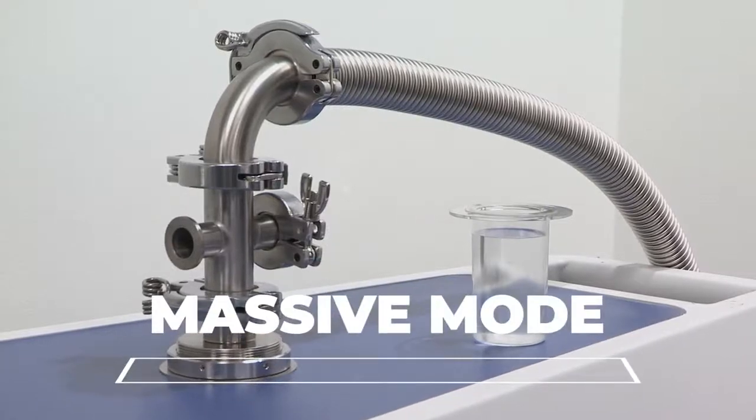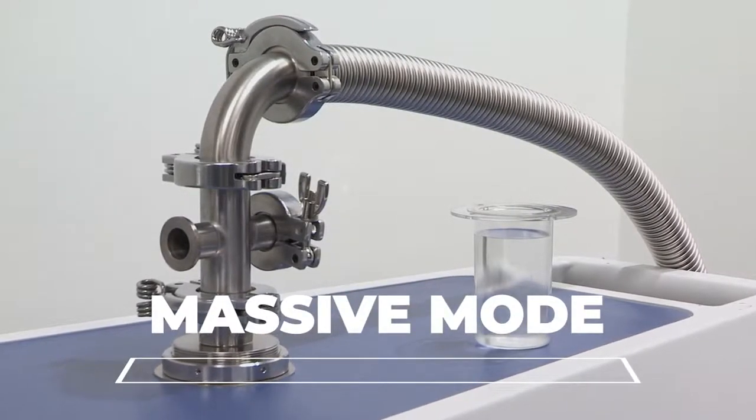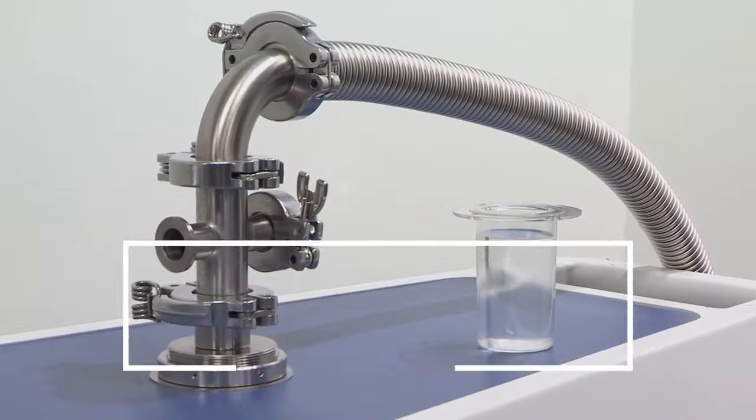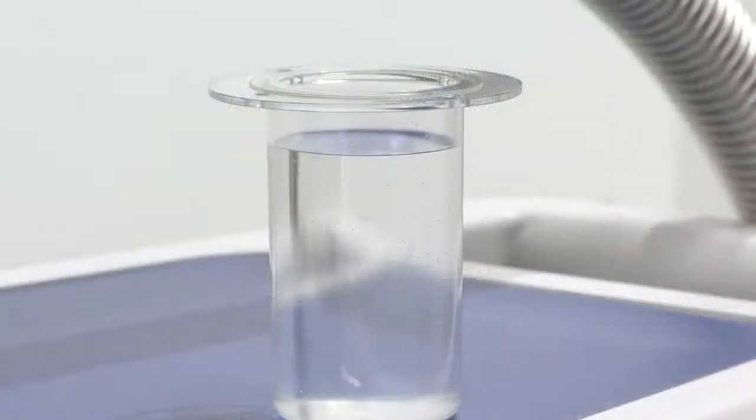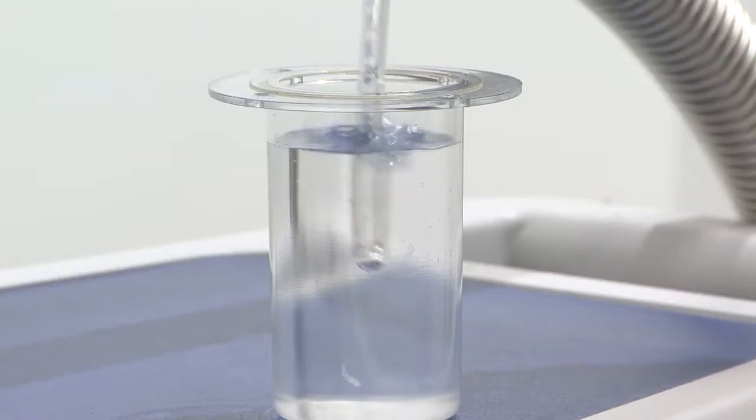Massive Mode enables you to start leak checking right from the beginning with the standard regular spraying procedure. For Massive Mode, 5 to 10 bubbles of helium gun flow shall be adjusted in order to quickly identify the locations of the leak.